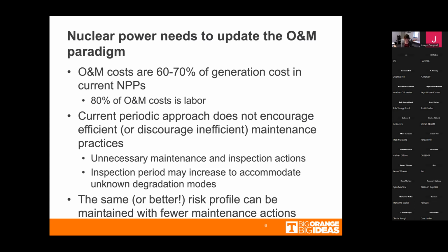EPRI, the Electric Power Research Institute, did a study of sensor calibration that showed that, comparing the as found and as left condition of sensors in nuclear plants, maybe 5 to 7% of the sensors were out of calibration at an outage, right? So over an 18-month period. And then after doing all of the calibration activities, about 3 to 5% of the sensors are out of calibration. And they're usually a different set of sensors.